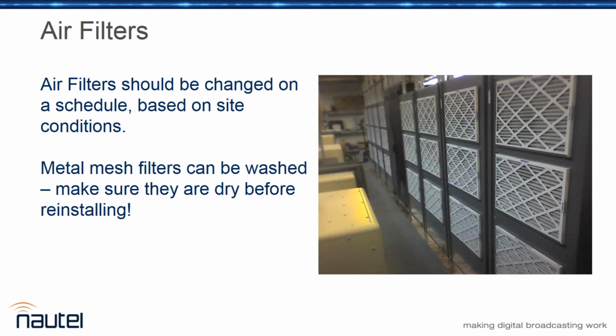As for air filters, change them on a schedule. We can't tell you exactly when they need to be changed, that's purely determined by your site. A well air conditioned site might go years between air filter changes, while forced air in the middle of a cornfield or down in the bayou might need changes every few days. It varies a lot from one site to another.